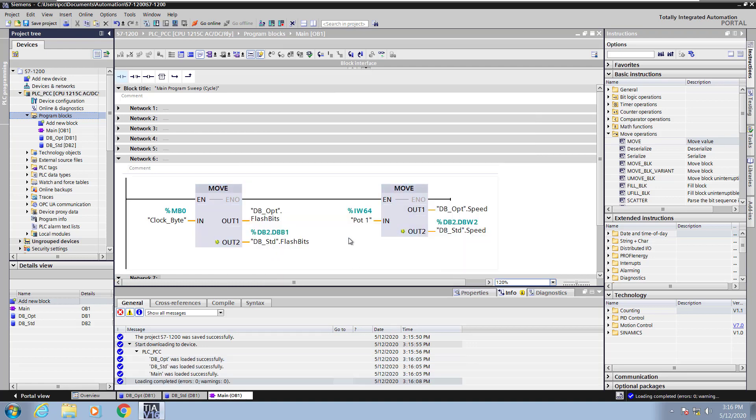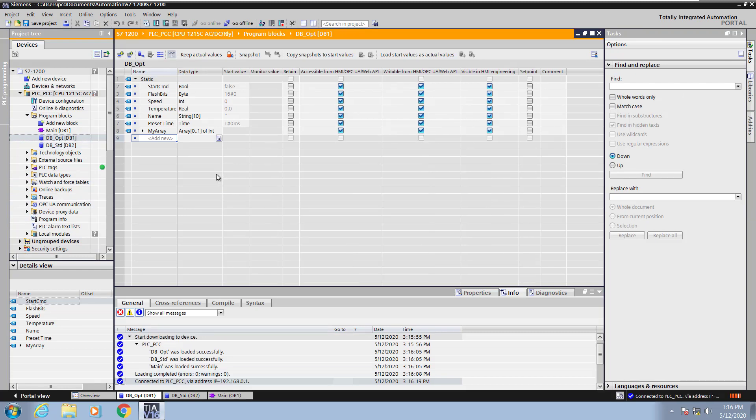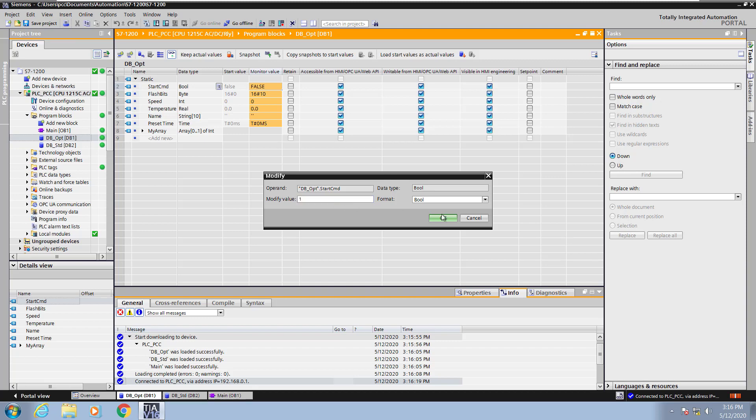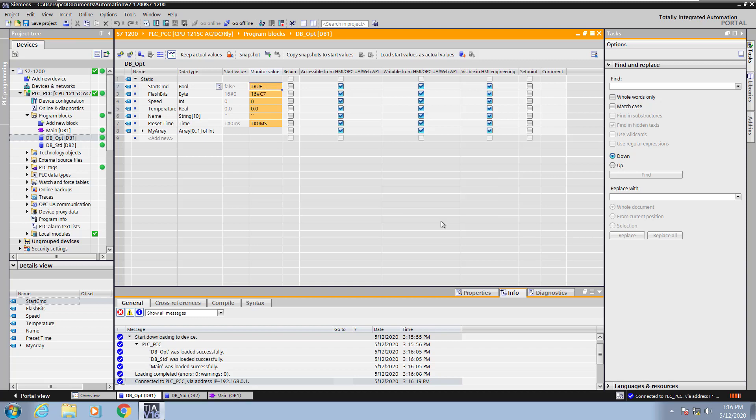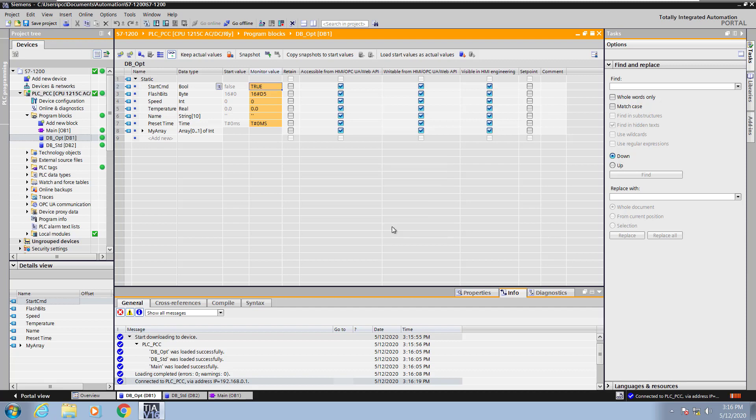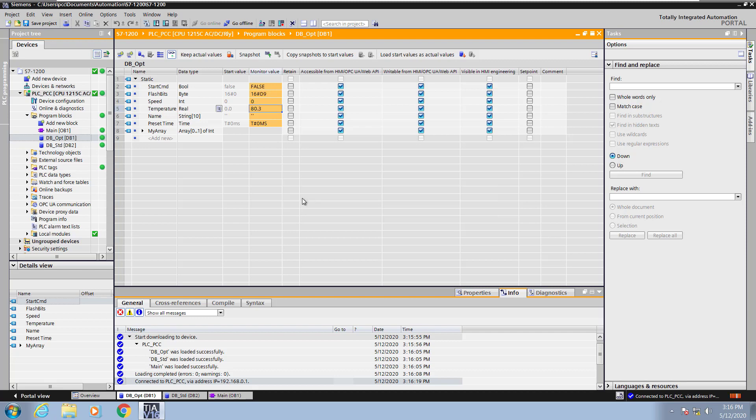Once the loading of the PLC program is completed in the program I can go into the project tree and I can select one of the data blocks for monitoring. So I will press my monitor all. This happens to be the optimized data block. I can modify values and I can view values. If I right click on a field I can select modify operand and I can type in a new value for that field. So in the modify value column for this boolean tag I'm entering one and press OK. For boolean values you can also double click and it'll bring up a toggle value command as well. So if I go to the temperature I can right click modify operand and enter in a real value now for this value. So I'm entering in 80.3 for the temperature.